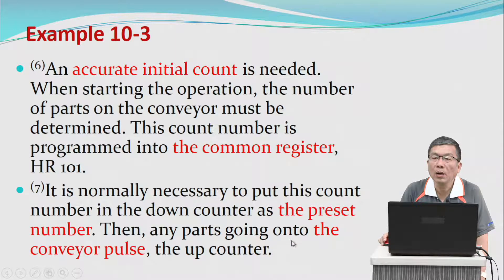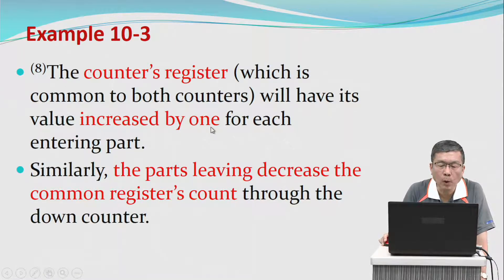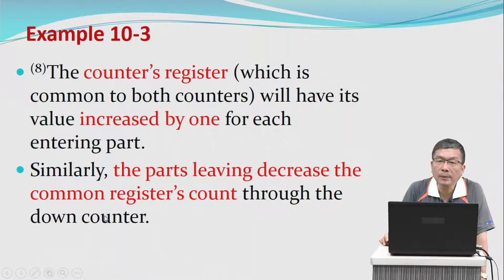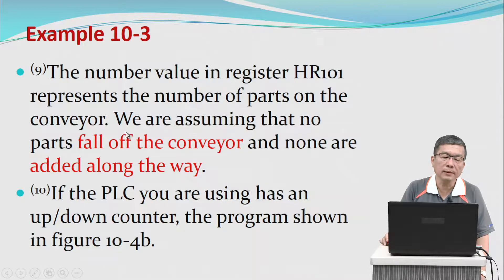It is normally necessary to put this count number in the down counter as the preset number. Any part going on to the conveyor increments the up counter. The counter register, which is common to both counters, will have its value increased by one for each entering part. Similarly, each part leaving decreases the common register count through the down counter. The value in holding register 101 represents the number of parts on the conveyor.